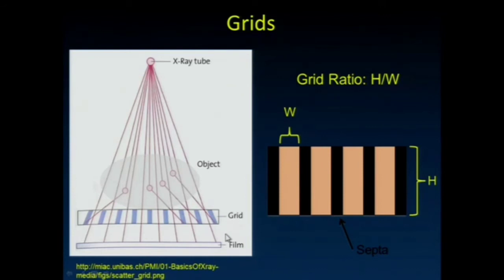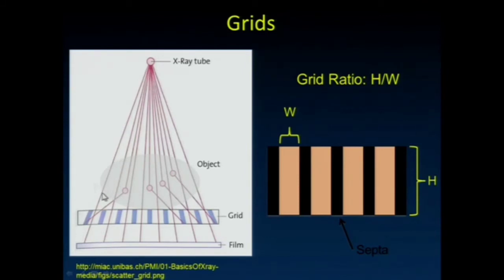Grids are another way to reduce scatter. Grids are very similar to the collimator used in nuclear medicine — I want you to keep that analogy in mind. In nuclear medicine, we use that collimator to focus the gamma ray energy onto the camera; here we're going to use it to reject scatter. The holes are lined up at a particular distance and angle to the X-ray tube, so primaries that aren't changed in direction should pass through the holes. Occasionally a primary may strike one of the pieces of lead and not make it through, so grids reduce primaries as well as scatter — but they reduce scatter much more than primaries, so our overall scatter to primary ratio gets much better.